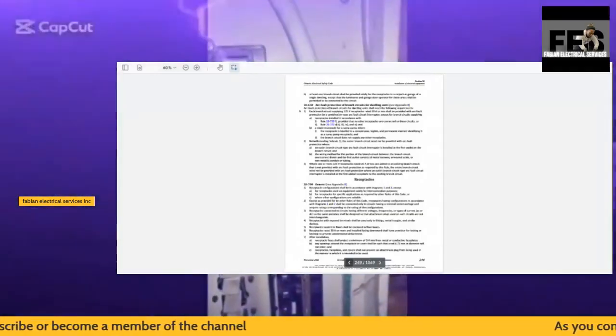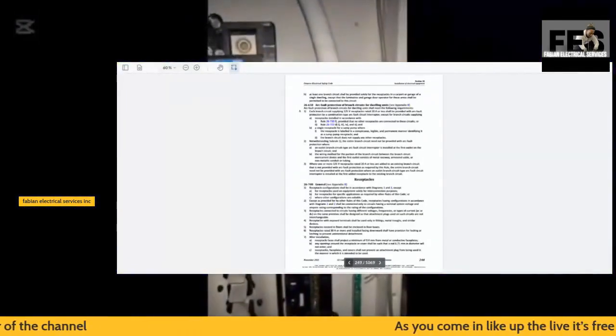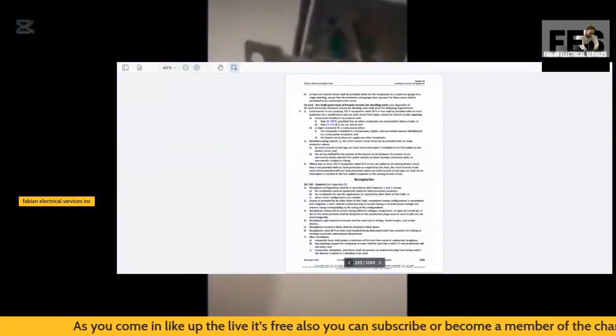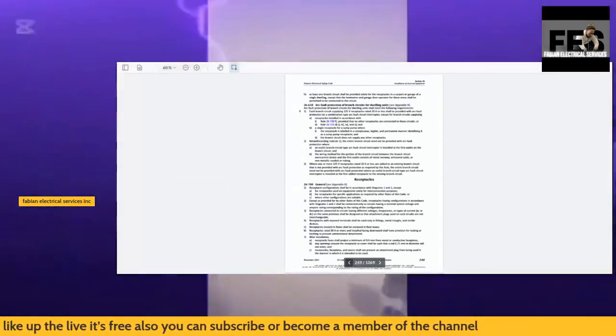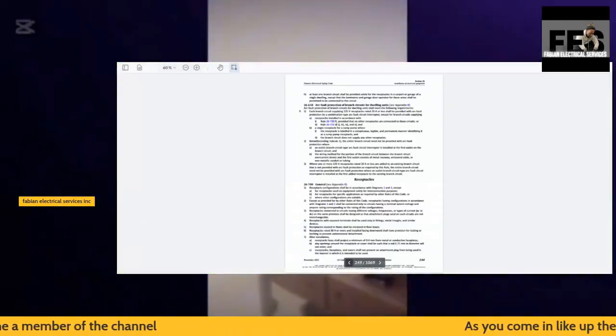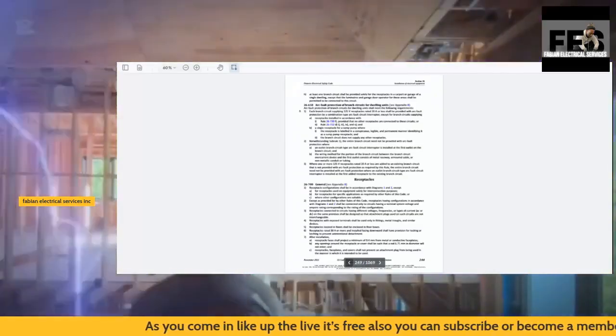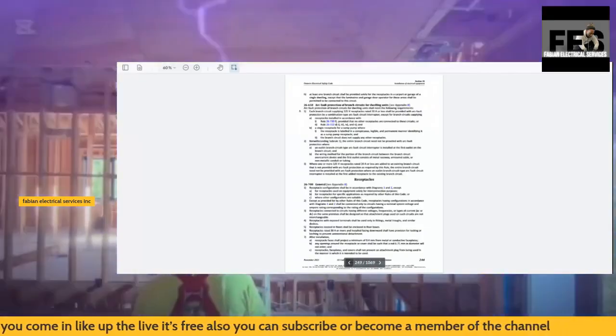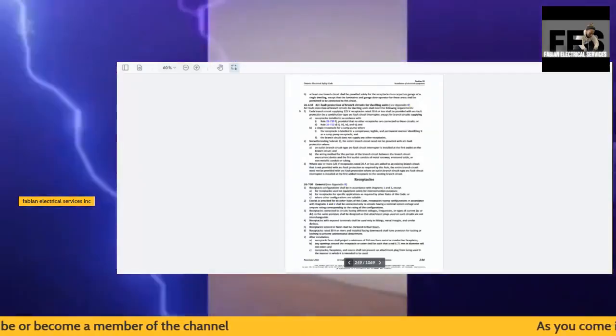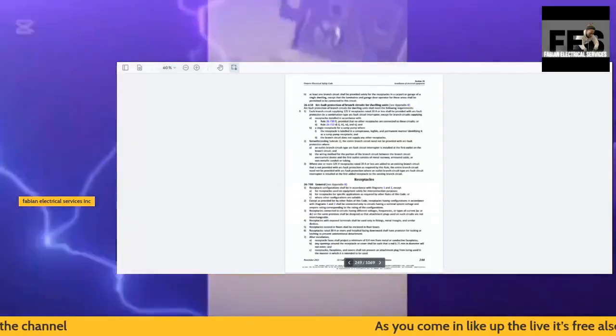Receptacle faces shall project a minimum of 0.4 millimeters from metal or conductive faceplates. Again, that is simply a rule that your faceplate has to be touching the actual receptacle. It has to sit on it in place. It cannot be coming off of the drywall with a space in between. Any openings around the receptacle or cover shall be such that a rod of 6.75 millimeters in diameter will not enter. Again, this is a code rule that we have to follow.